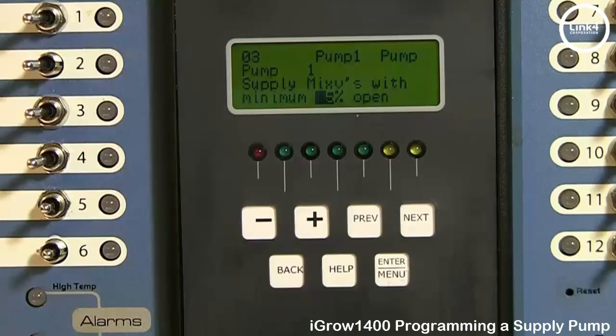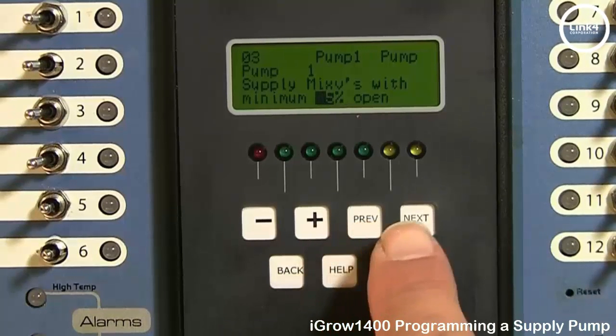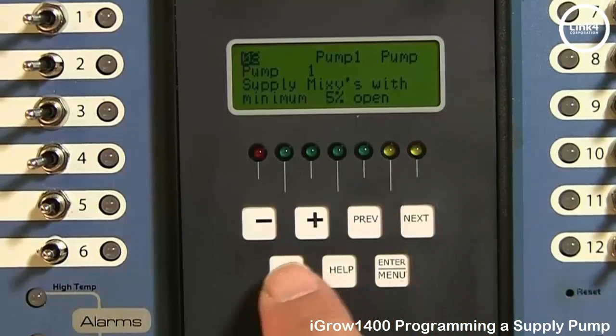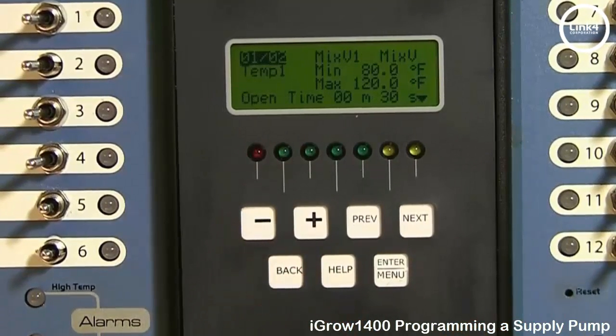the pump will turn on and remain on until the mix valves associated with this pump have closed beyond this threshold of 5%. And once it hits below that 5%, the pump will turn off. Now, let's go ahead and put this output to the test. Simply hit next till we get to the 03, and then minus to get to the 0102 mix valve output.